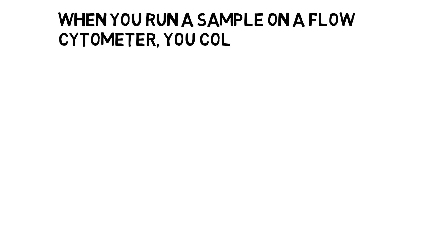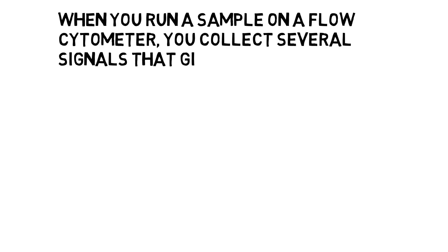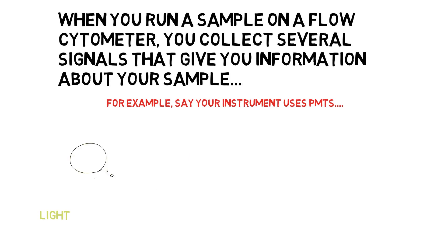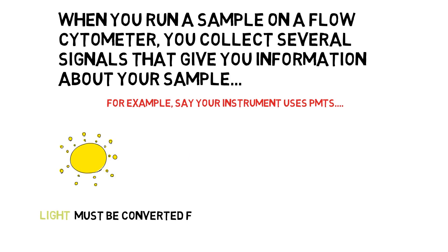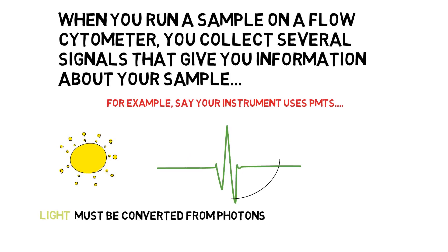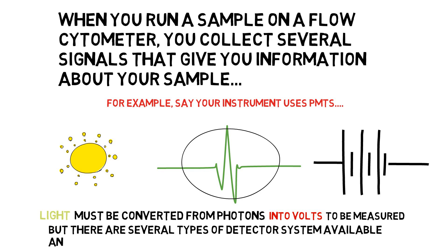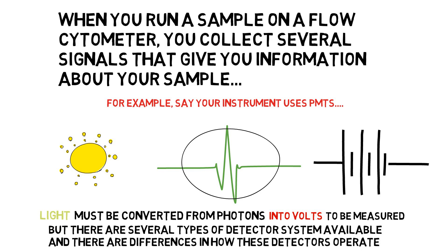When you run a sample on a flow cytometer, you collect several signals that give you information about your sample. For example, say your instrument uses PMTs. In this case, light must be converted from photons into volts to be measured. But there are several types of detector systems available, and there are differences in how these detectors operate.